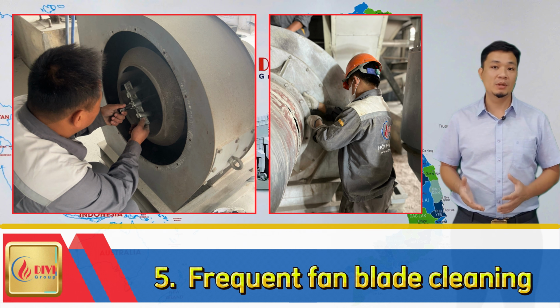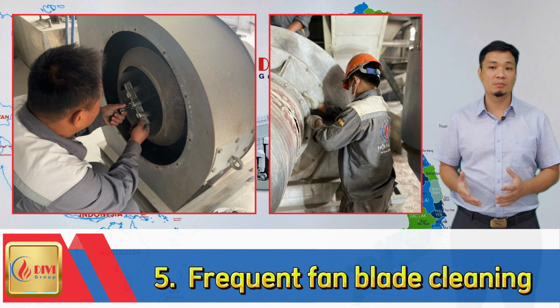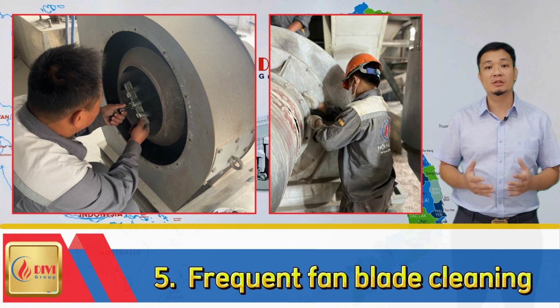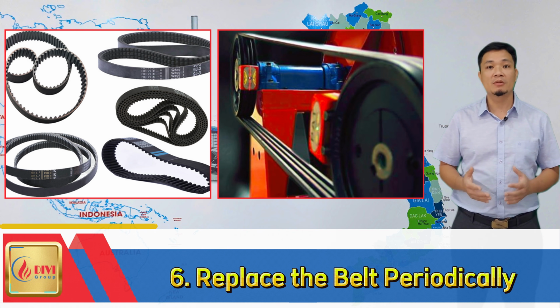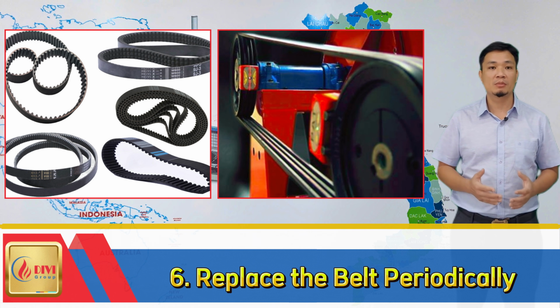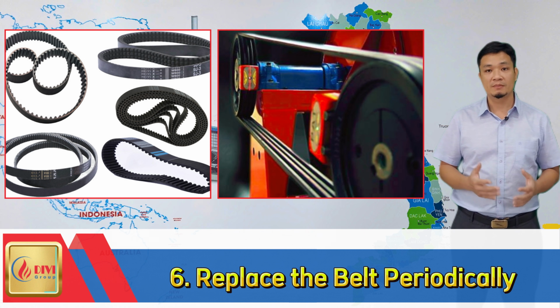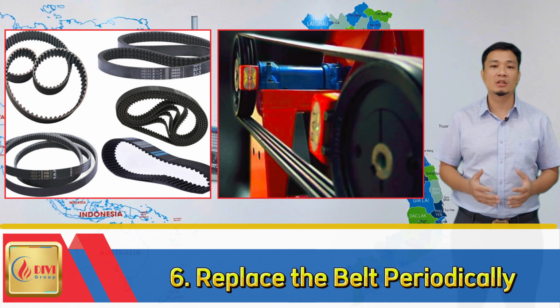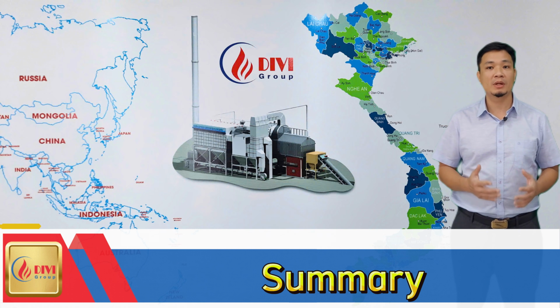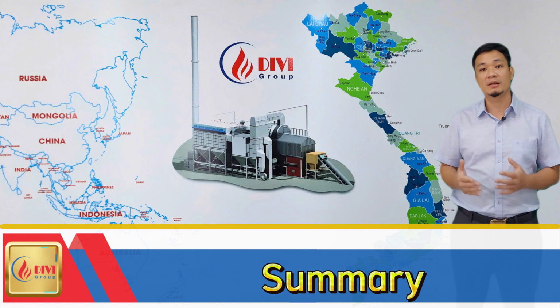5. Frequent fan blade cleaning. Inspect and clean accumulated dust to avoid imbalance, reduced efficiency, and bearing damage. 6. Periodic belt replacement. Inspect and replace the belts when wear or damage is detected, especially in facilities with continuous operation. These are the 6 fundamental steps for maintaining boiler-induced draft fans.